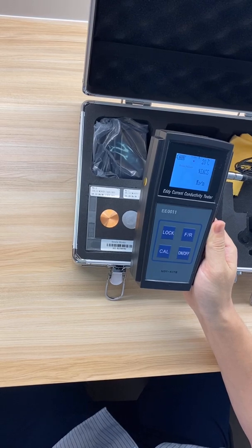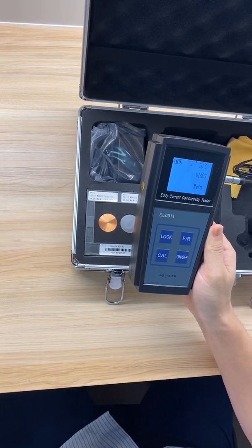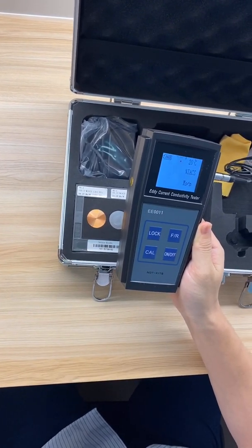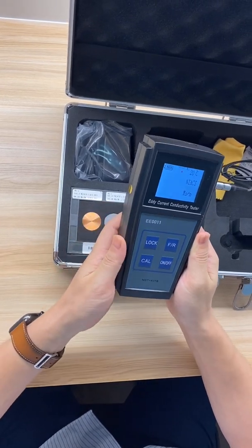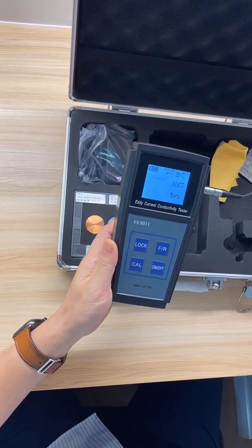Because room temperature affects the conductivity, leave the instrument in the testing environment for 15 minutes before calibrating.